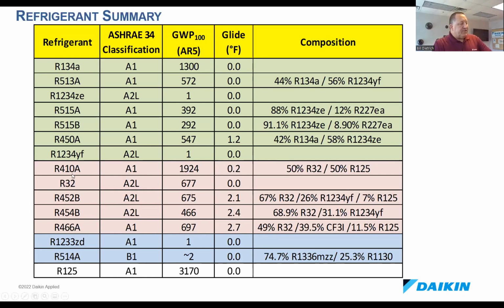What's interesting is we use R410A all the time, right, as a single fluid. But under ASHRAE lingo, it's technically considered a blend, but not an azeotrope. But you can see it has a relatively small glide of 0.2 degrees Fahrenheit. So for all practical purposes, we can treat it like a single working fluid.